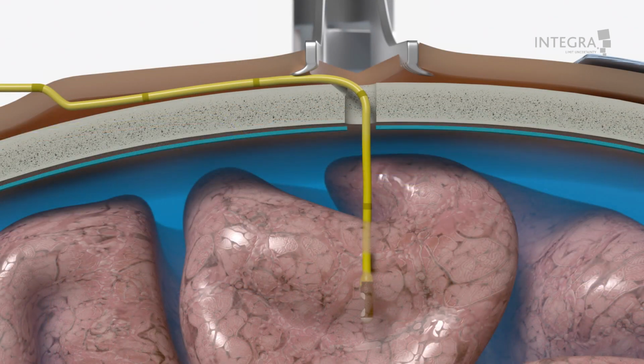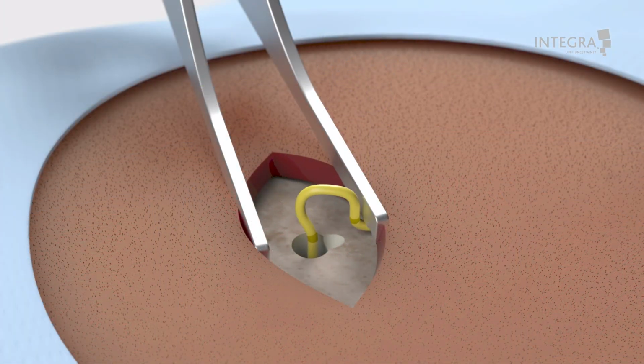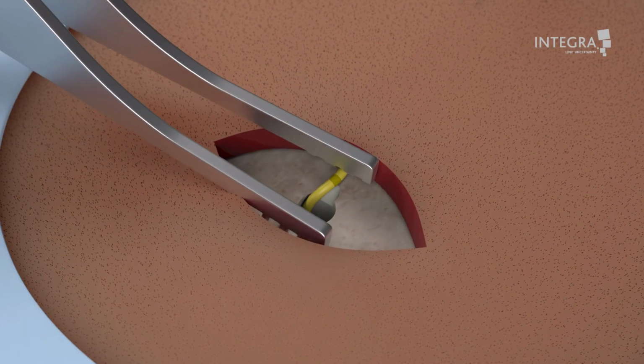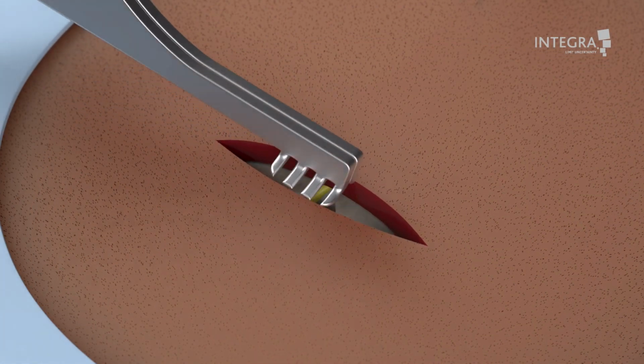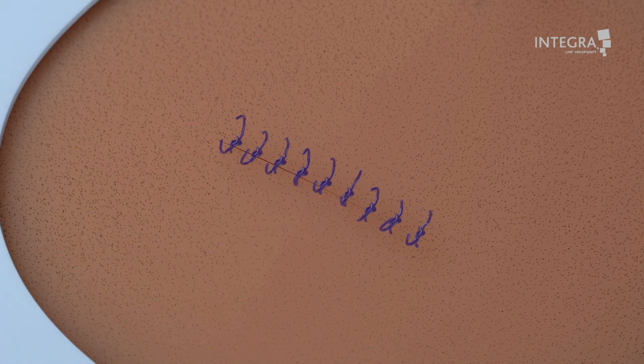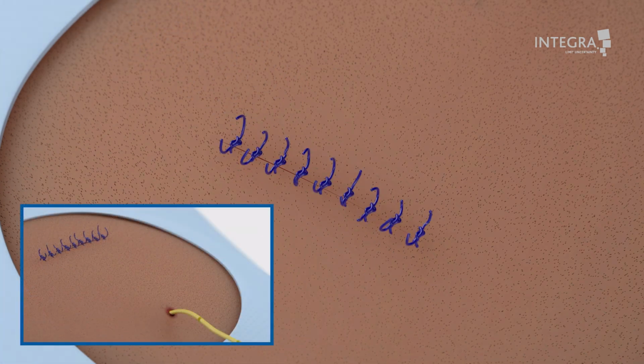For intraparenchymal ICP monitoring, place the tip of the ICP sensor into the parenchyma through the puncture in the dura until the kink is at the edge of the hole, as shown in the picture. Carefully pull back the excess ICP sensor tubing. Remove the retractor. Verify hemostasis in the insertion area, and then suture the incision site closed. For additional strain relief, make a small loop with the excess ICP sensor tubing and tie the loop down.